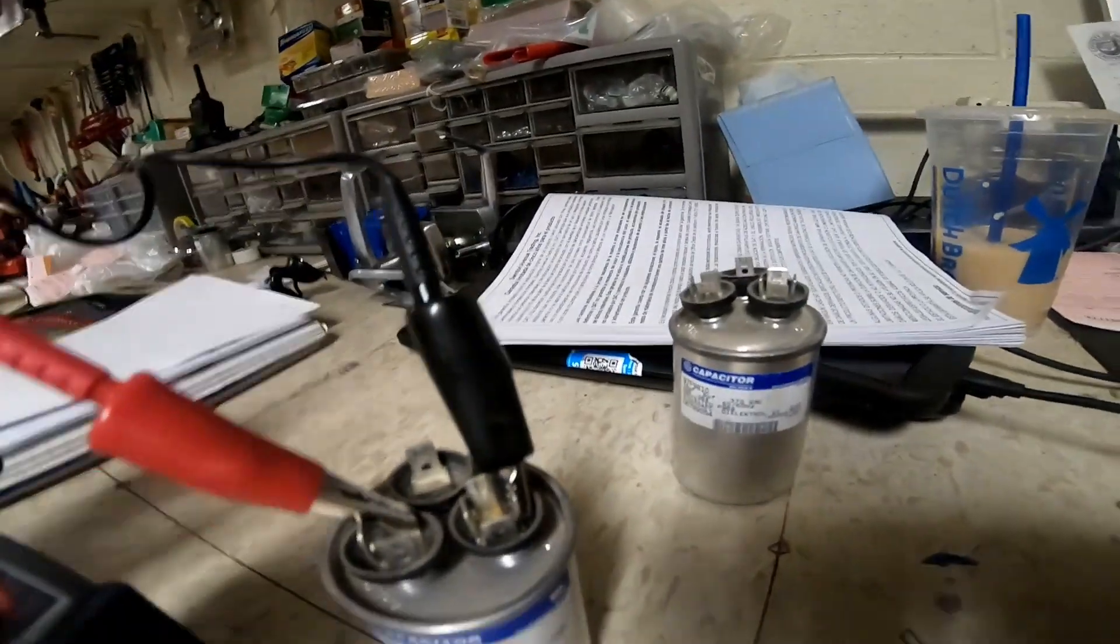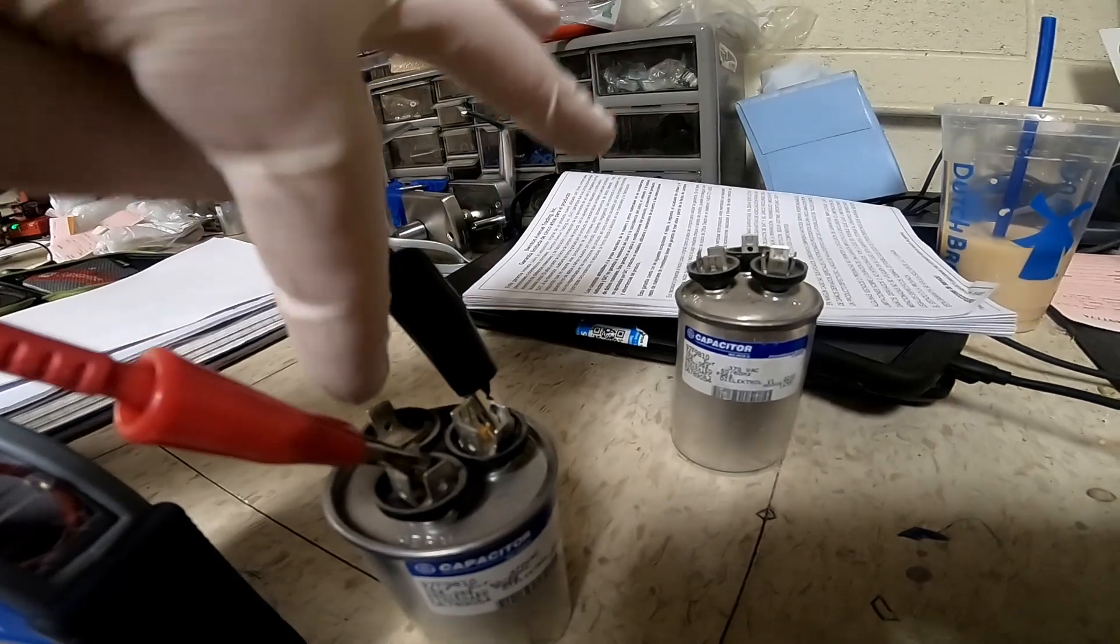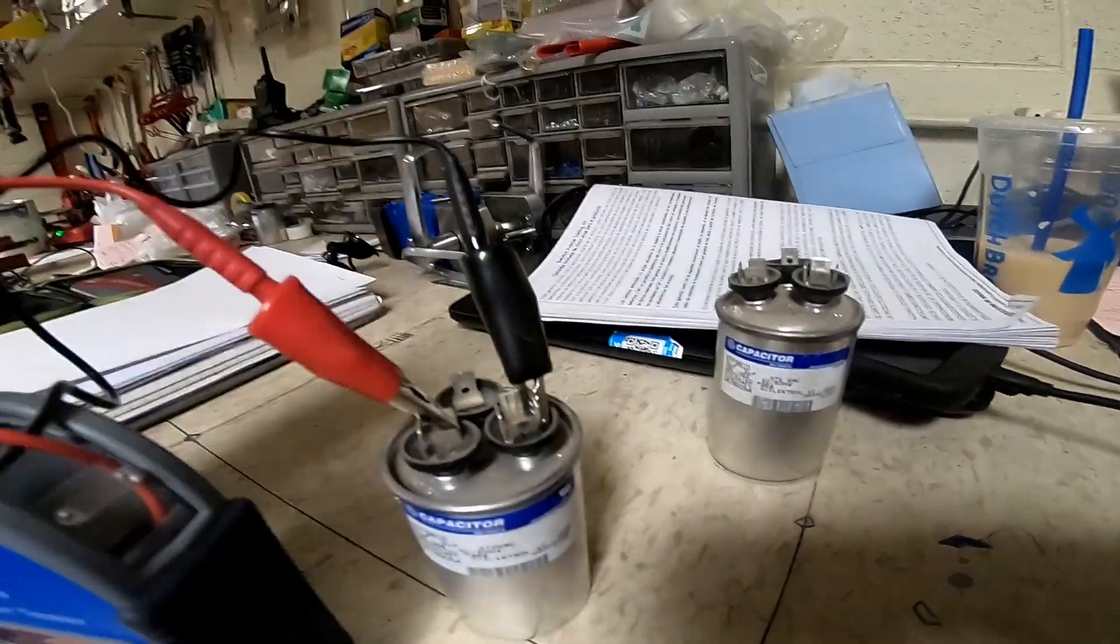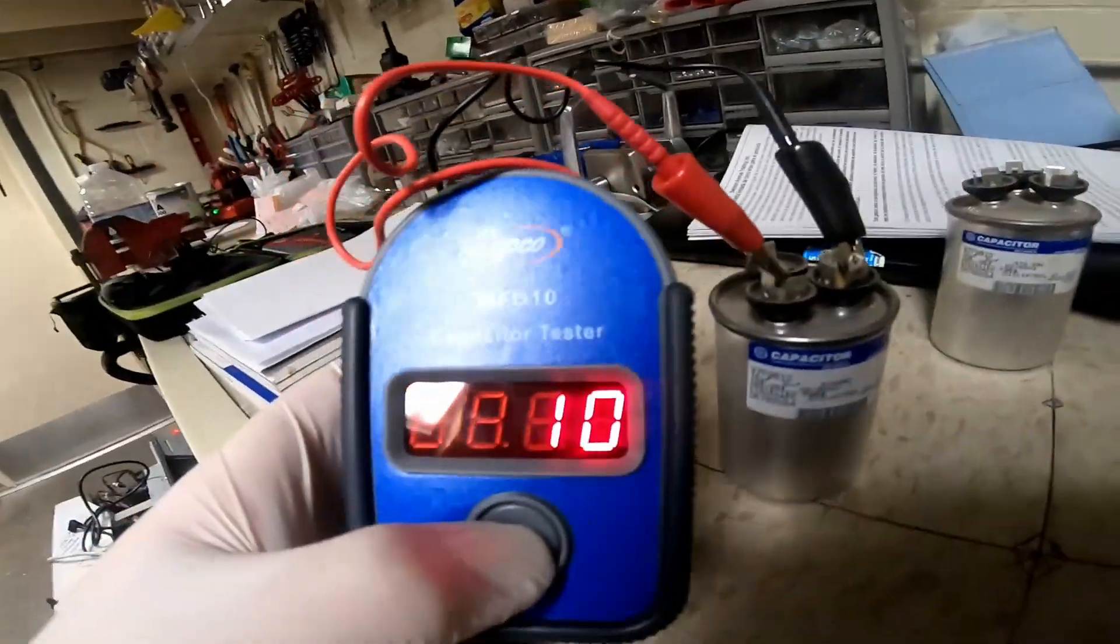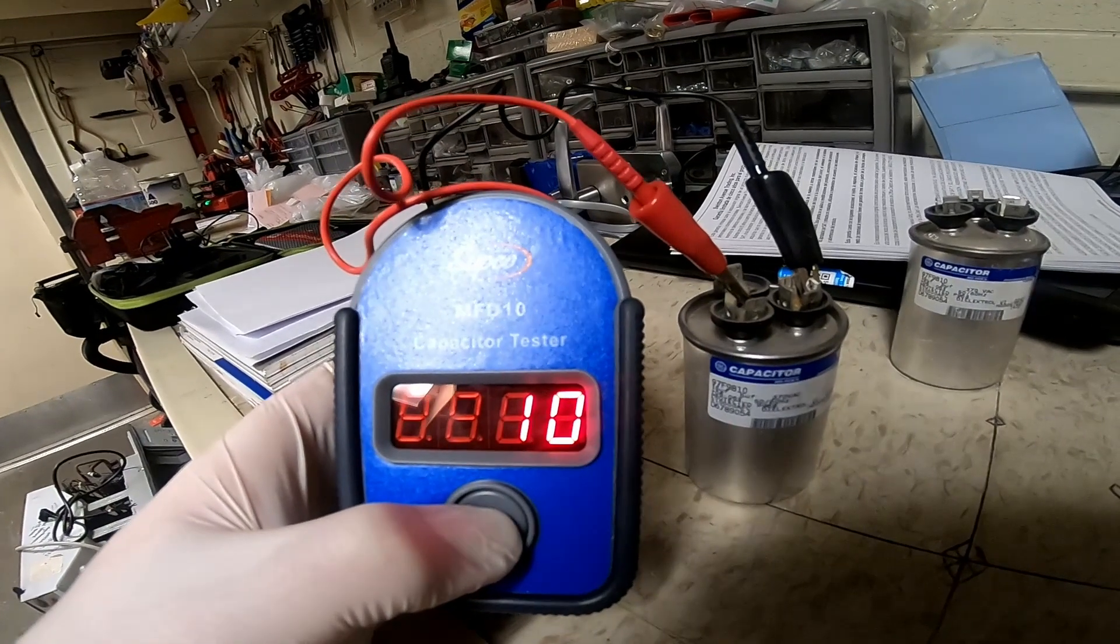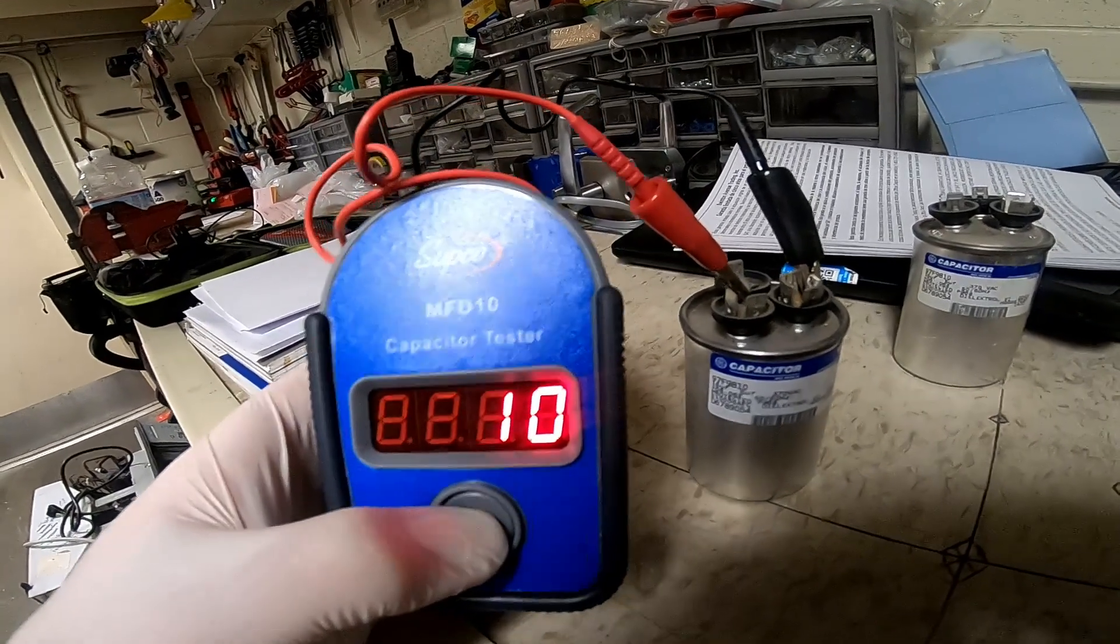You leave it on the common and you move the red from one to the other capacitor. This one's supposed to be 15 plus or minus 6 percent, and you can see that it's at 10, so it's out of spec on that one.